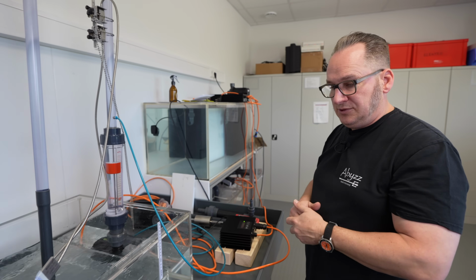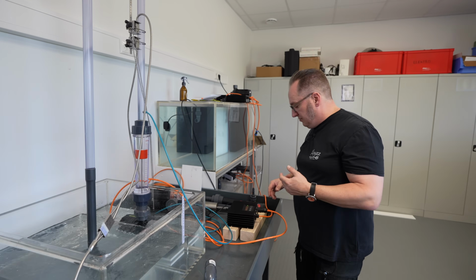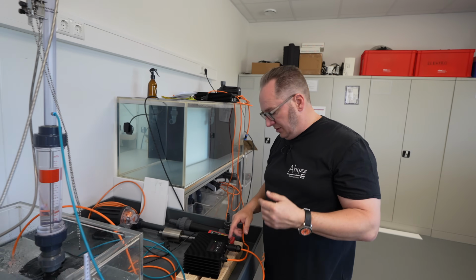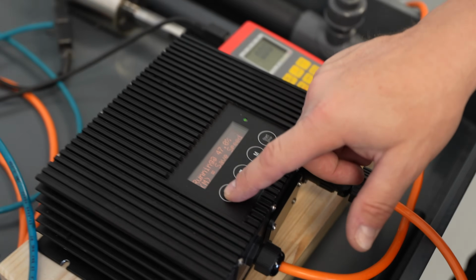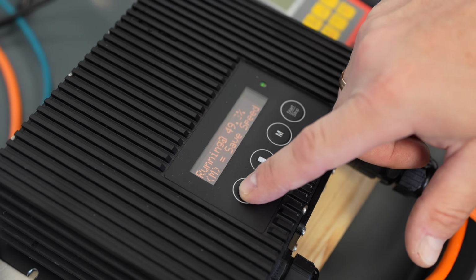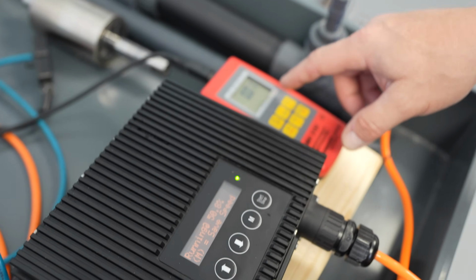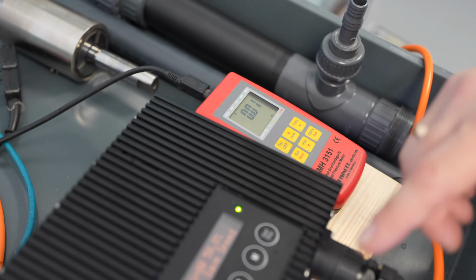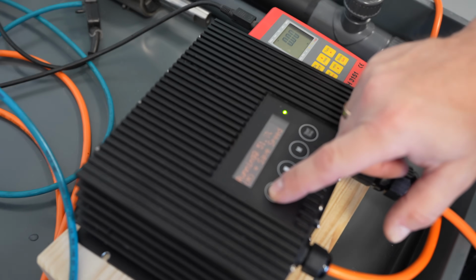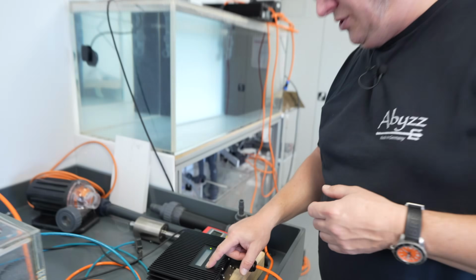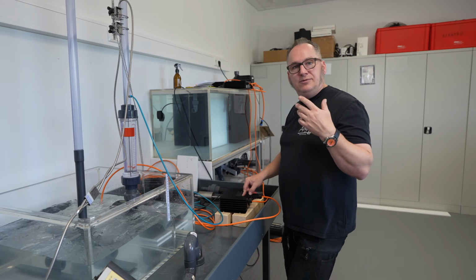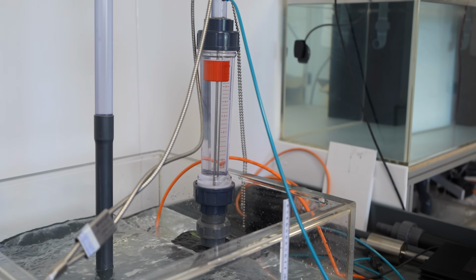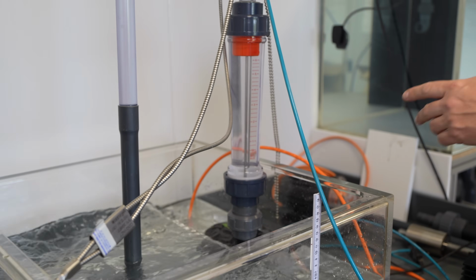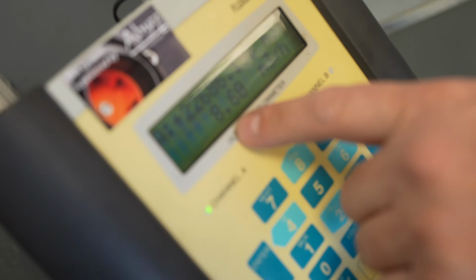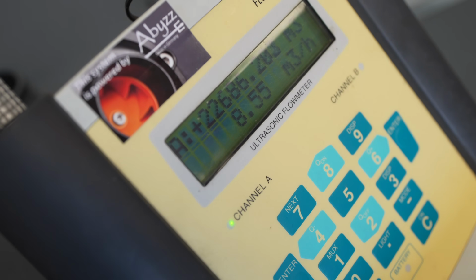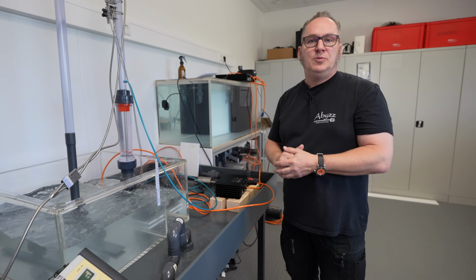Now, if we go up to a higher speed, we'll see that there's not a maximum coming out that the pump would be able to do. So we'll dial this up. Oh, by the way, the pressure was around 0.01 bars, which is roughly 10 centimeters in pressure loss. Now, if we dial this up and raise the turnover rate, we're exceeding this little measuring device. So the pump is running at 100% with 200 watts. We're only getting 8.6 cubic meters per hour.